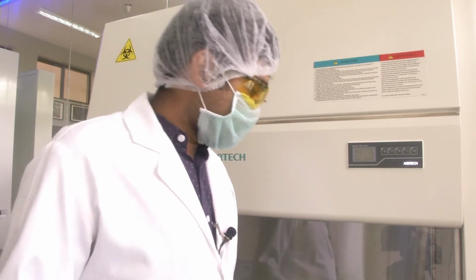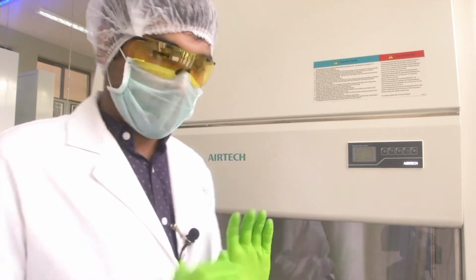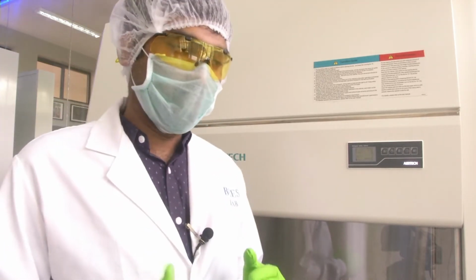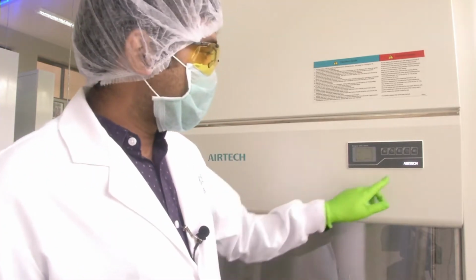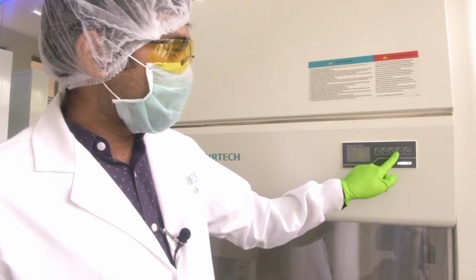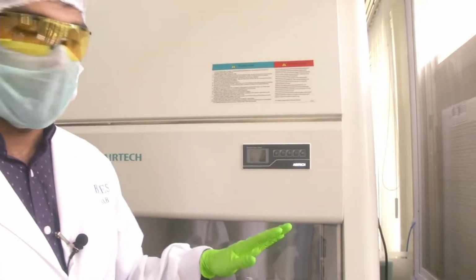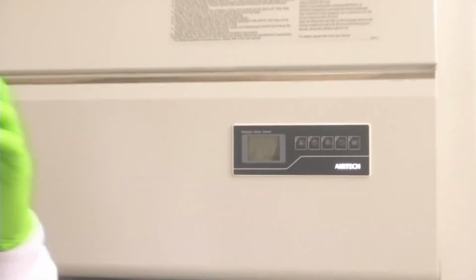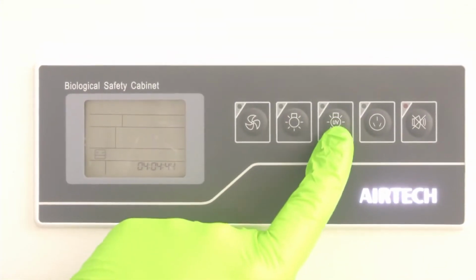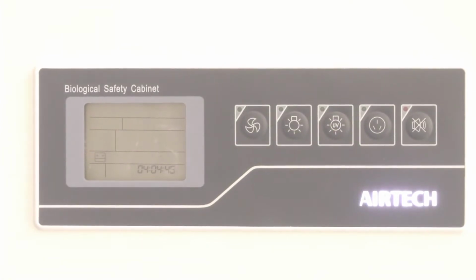There are a few things provided on the biosafety cabinet that we need to do before we start using it. If you see the knobs, there are five knobs provided. The major one is a UV knob in the middle. Whenever we do not use the cabinet, we need to have the UV light on. If you see, the UV light has come on and the color inside has changed. What does this UV light do?